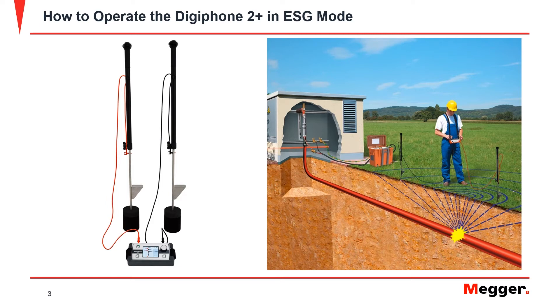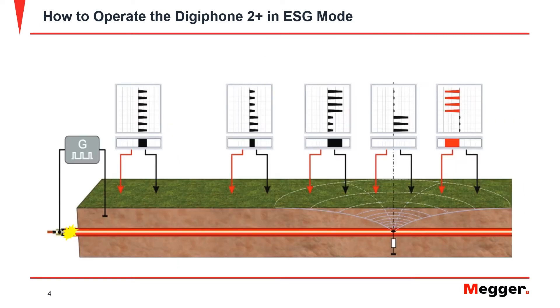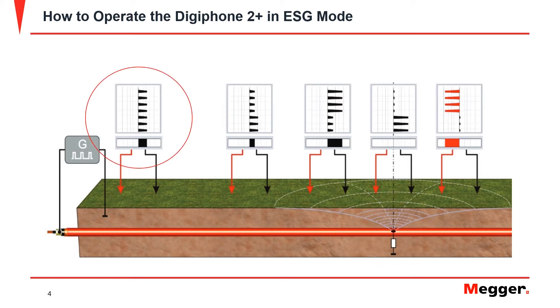It is important to ensure that the orientation of the probes remains consistent during the fault location process. As voltage gradients induced by the current flowing back from the fault position exist around the earthing point of the generator, the measurement values near this point might be elevated. However, the deflection direction will also indicate the direction of the fault position at this point.